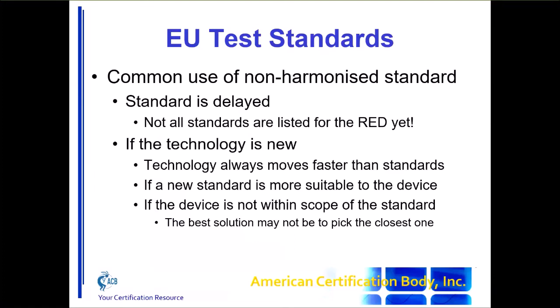Or if a standard is found to be more suitable for a device that has just been written and the manufacturer wants to use that new standard, then that might be a reason why they'd use a non-harmonized standard. Or if there is simply no standard for their product, then don't just pick some other standard that's not really for your device and use it anyway - that would not be correct. You would have to create your own test plan or test standard.